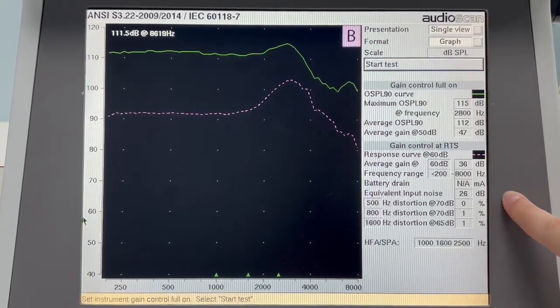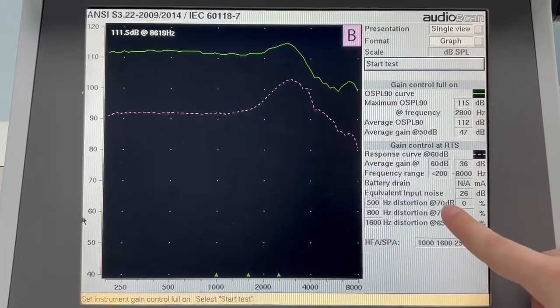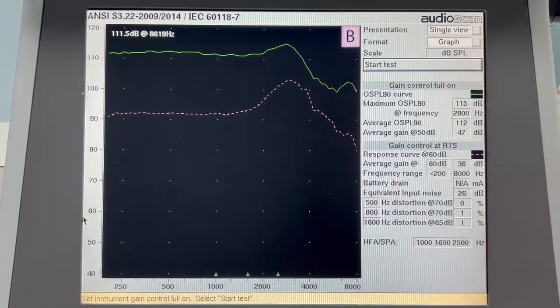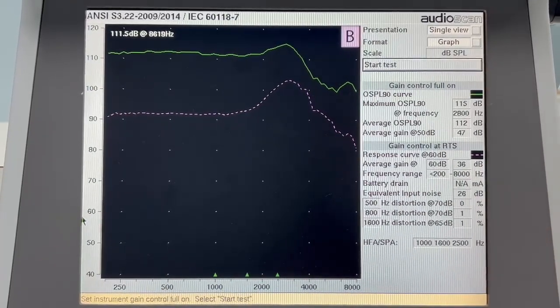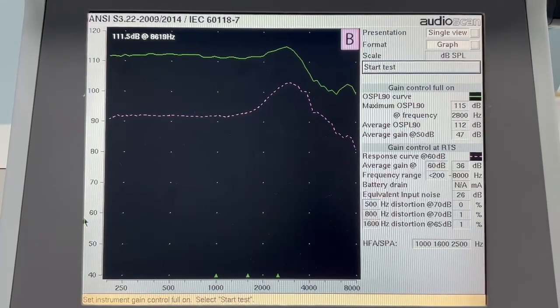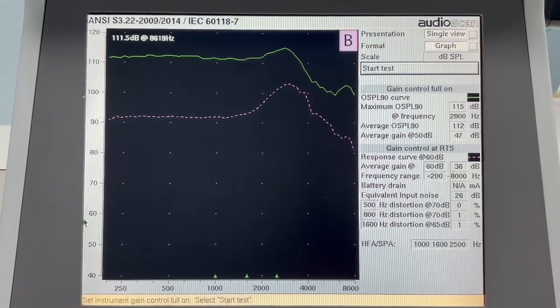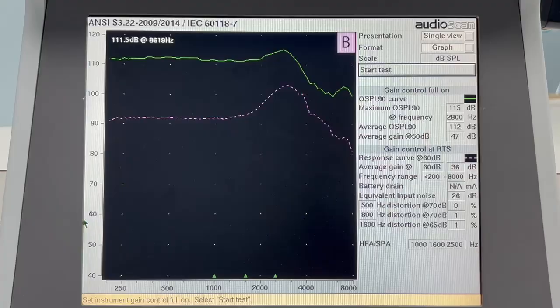For this specific manufacturer, the equivalent input noise value is 19 decibels, so this is above that specification. In this case, the hearing aid may produce more static, and therefore would need to be sent back to the manufacturer to be checked.